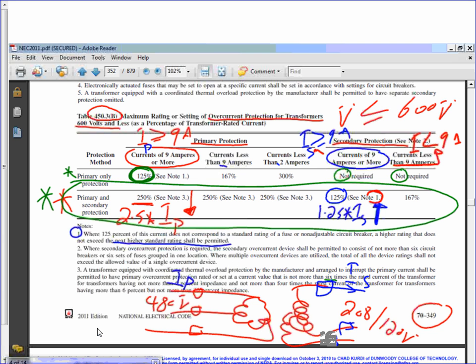Why am I going to multiply by 250? One more time. This table, you use it to size the overcurrent protection device for transformers. This first row is called primary only protection. That's if you only have circuit breakers on the primary side. We will have primary and secondary.